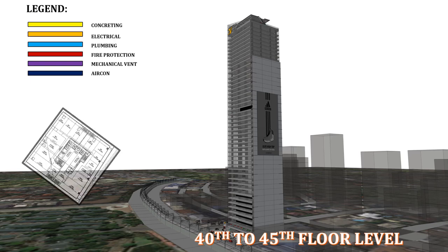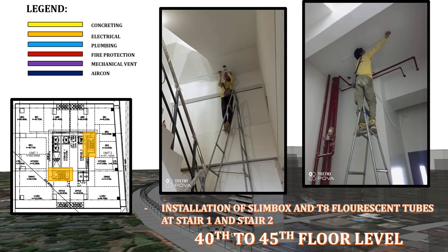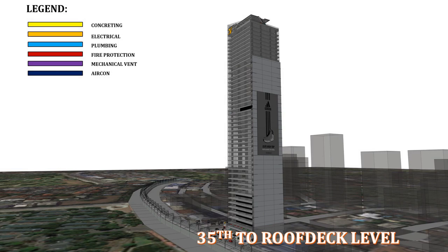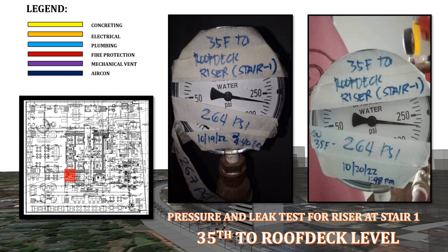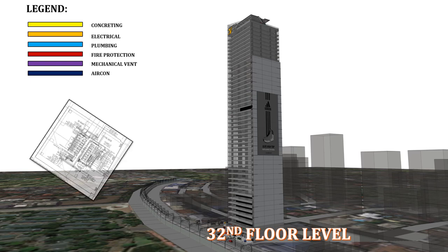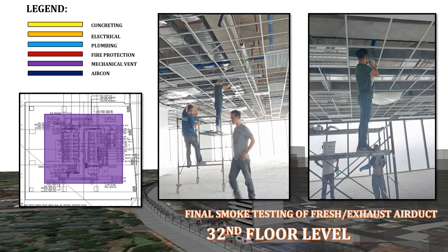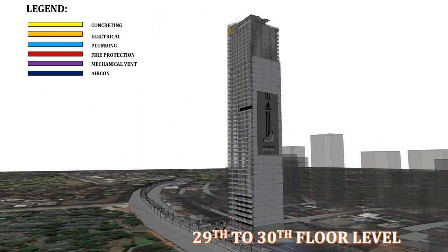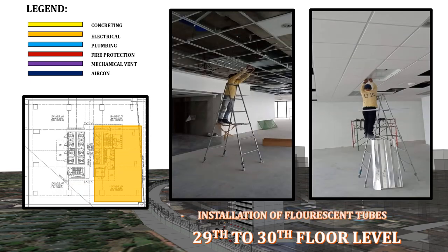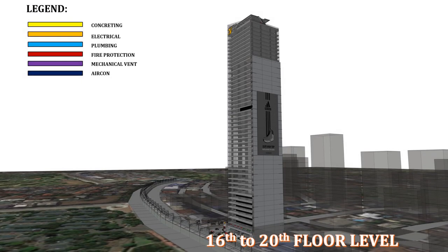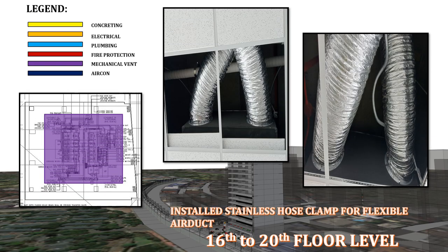At electrical works, the accomplishments at 40th to 45th floor level is the installation of ceiling box and fluorescent tubes at stair 1 and stair 2. At fire protection works, the accomplishments at 35th floor level is the pressure and leak test for riser at stair 1. At mechanical works, the accomplishments at 32nd floor level is the final smoke testing of fresh air exhaust air duct. At electrical works, the accomplishments at 29th to 30th floor level is the installation of fluorescent tubes. At mechanical works, the accomplishments at 16th to 20th floor level is the installed stainless hose clamp for flexible air duct.